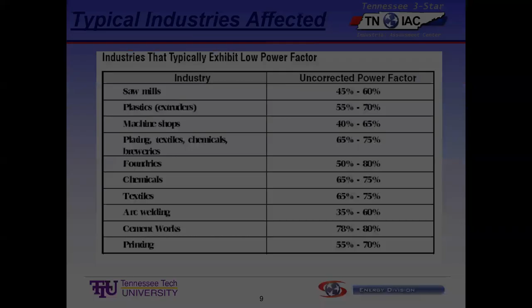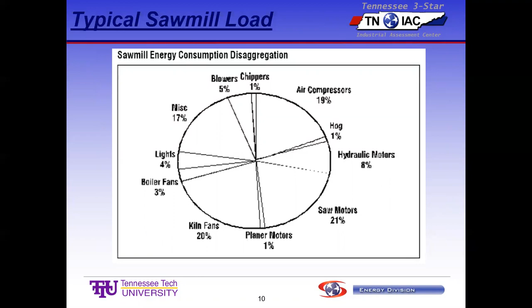Okay. This shows, say, a sawmill is a good example. A lot of this type of equipment, stuff like these saw motors and chippers on a big saw in a sawmill, they don't start and stop it. It's this big saw. They just start it and it runs all day long. And it occasionally cuts a board. It's sitting there, a log comes along and zzz, zzz, zzz, and then it sits there waiting for the next log. And then zzz, zzz. So it spends a lot of time running unloaded. Unloaded motors are a major contributor to this. Oops. There we go. And that's what this shows.